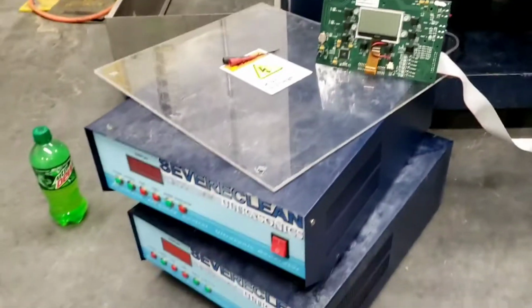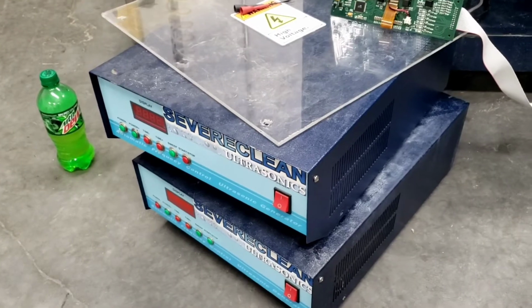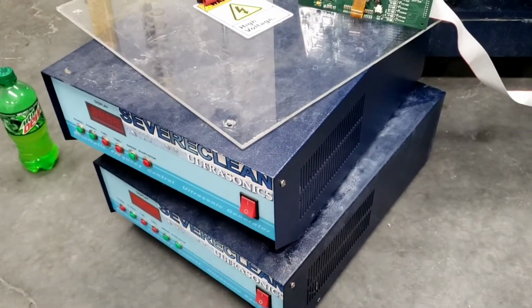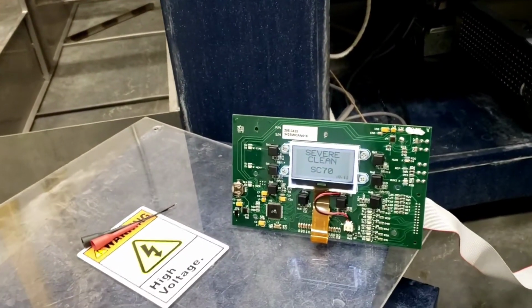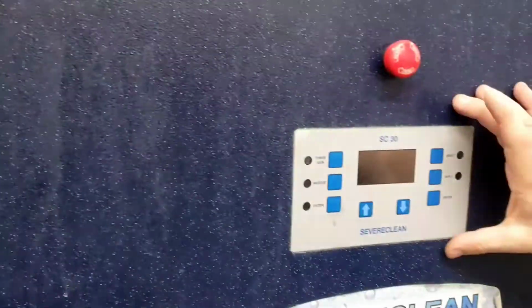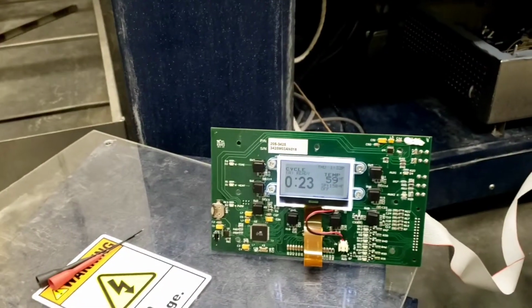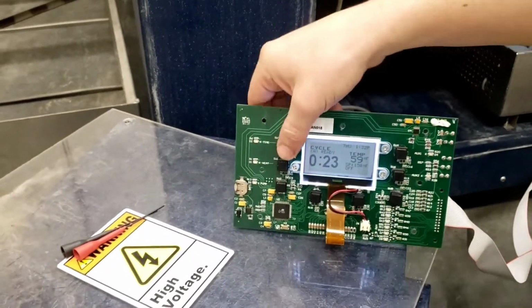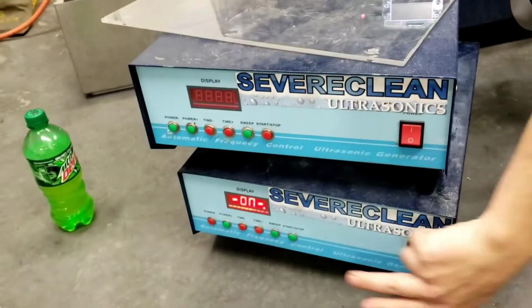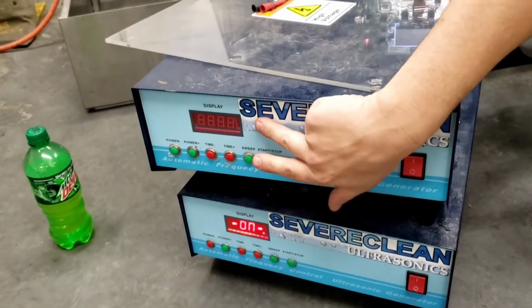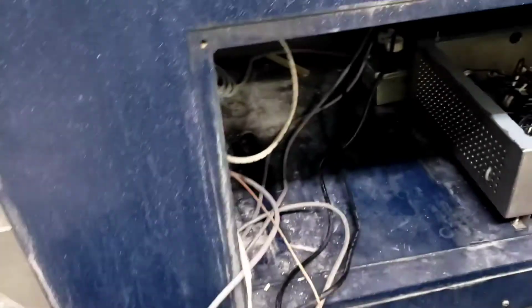But obviously the generators are not on yet. We're having a generator fault, which means one of these is not turning on. We believe these are good, and we'll walk through this. So he's going to go ahead and turn the main power on, which lights that up. That would normally be up in there, but we have it down here. Now he's going to hit the generator button, which is normally the top one there. If you look, the bottom generator's on.